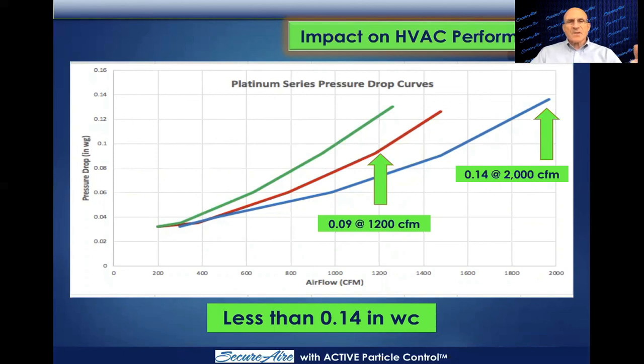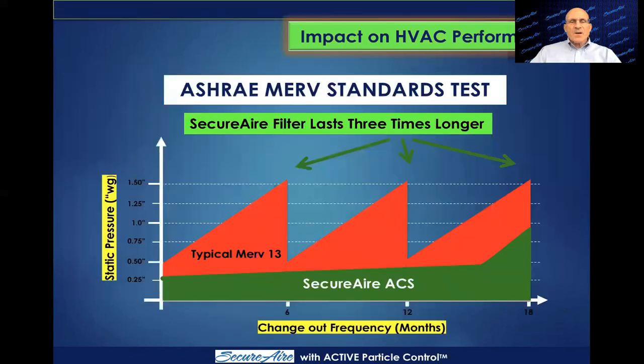And it's not only initial static pressure that's low, but our cartridge will hold 3 times more contaminants than even a MERV 13 filter will, meaning that it'll last 3 times longer. So it's going to be very common that you experience 6-month life without a significant increase in static pressure. You could even go a year.